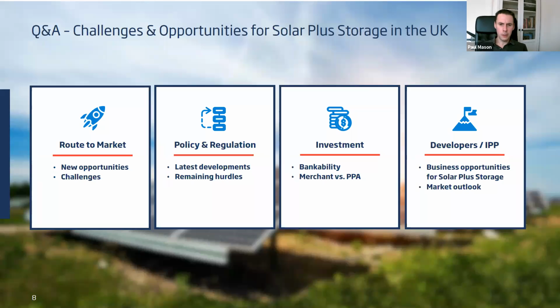So right now, if you match the capacity of a battery, so you've got for example a 20 megawatt solar PV matched with a 20 megawatt battery, that battery will be earning about 15% less revenue than a standalone equivalent. But I think you could bridge that gap considerably by moving procurement closer to real time, and also by taking a more aggressive stance in optimization. So I think evolving the procurement of ancillary services will help in that respect. But I think also evolving attitudes towards how you give priority to the two different assets on the grid connection can help the business case as well.